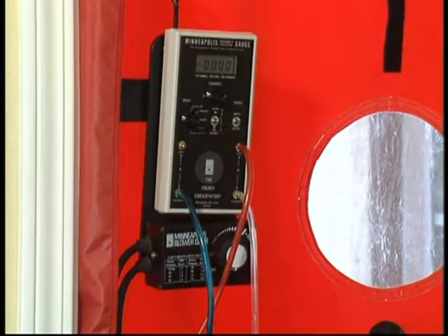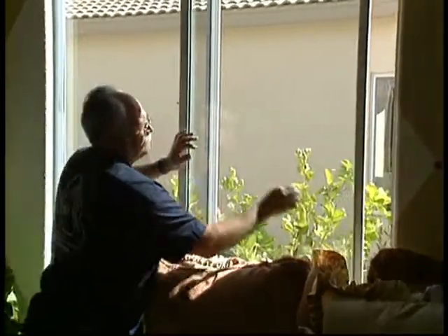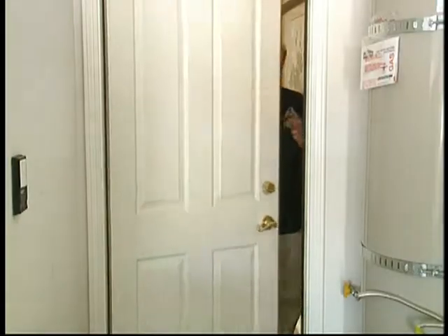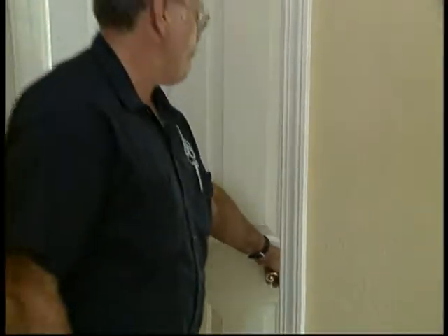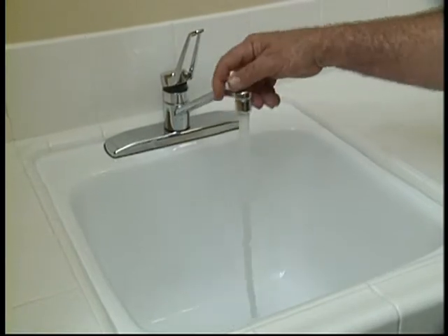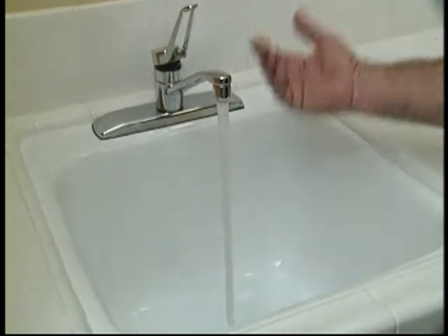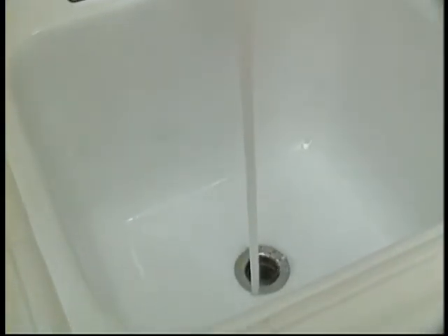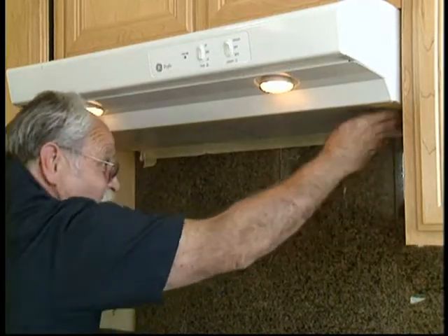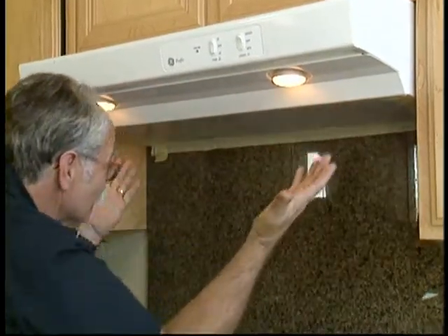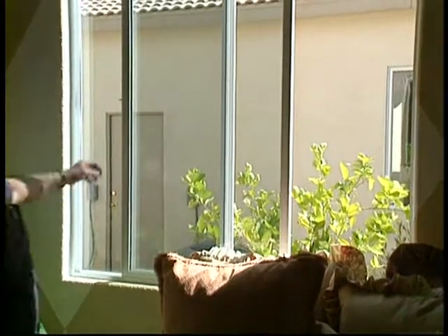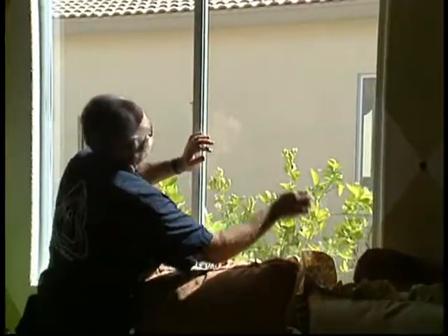When I come out to the house, Steve, I walk around, familiarize myself with the house, and then I start preparing the house for the test itself. Make sure that all the exterior windows are closed, all the exterior doors are closed, all the interior doors are open because we want to measure every room, the whole house. And I check plumbing traps to make sure they're full of water. And any exhaust fans that have dampers, make sure that they're closed off, because we want to prep the house for its normal operating conditions.